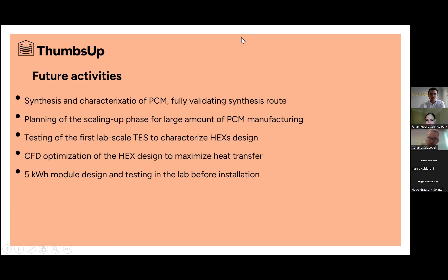We have two questions. The first is, what is the maximum storage duration for the solution? We target 3 hours storage duration as a minimum, which is a target of the call for proposals, with a charging rate of 3 kilowatts. We are looking at intraday solutions, meaning up to 24 hours of storage before self-discharge effects kick in, and before economic effects kick in, since if the duration is too long we don't get sufficient cycles and therefore lower revenue. So 3 to 24 hours as a ballpark figure.